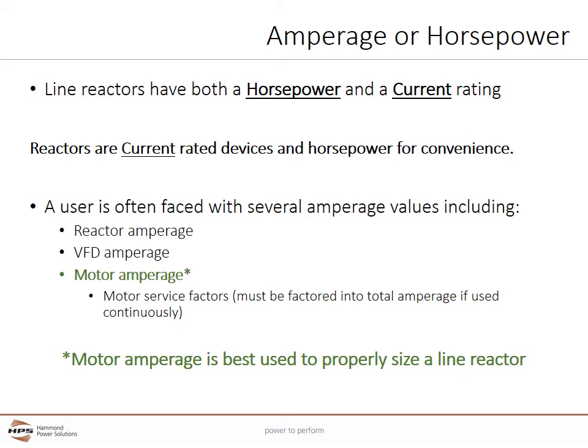Line reactors have both a horsepower and a current rating. Ultimately, reactors are current-rated devices. Horsepower ratings are for convenient selection. HPS's horsepower ratings typically follow the NEC motor amperage charts. A user is often faced with several amperage values including the reactor's amperage, the VFD's amperage, the motor's amperage, and the motor's service factor. The motor's service factor must be factored into the total amperage if the application will use this extra capacity continuously. In most cases, the motor's amperage is best used to properly size a line reactor.